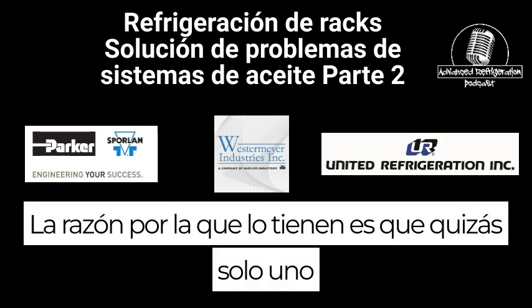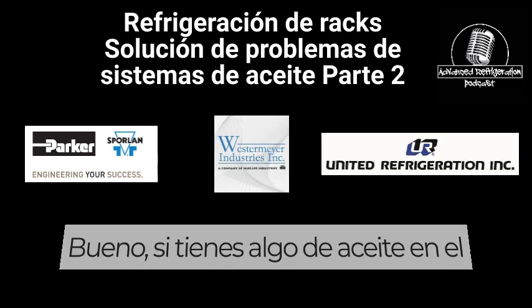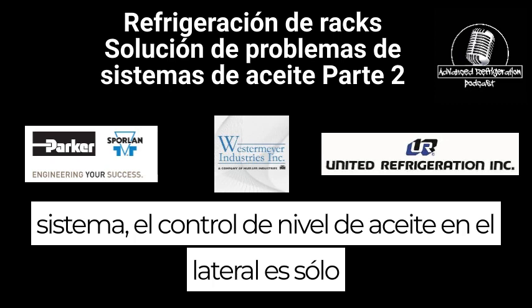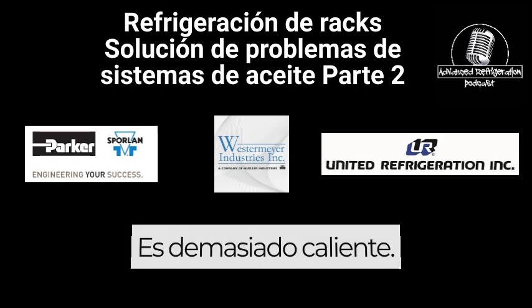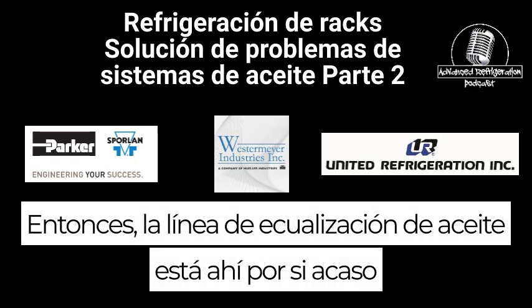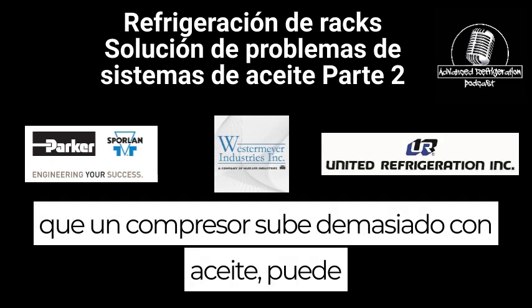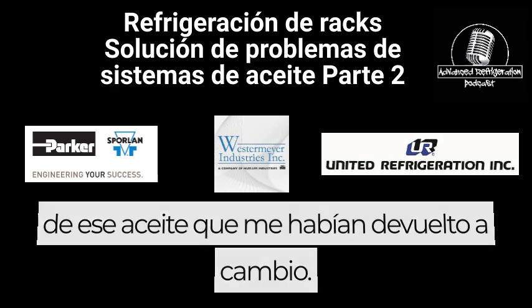The reason why they have it is you might only have one compressor running all the time under a low load situation. Well, if you do have some oil out in the system, the oil level control on the side is only going to fill it up when it's low. It's not going to be able to remove that oil if it's too high. So the oil equalization line is there in case that one compressor gets too high with oil, it can share the oil with the other compressors and expel some of that oil that hadn't gotten back in the return.